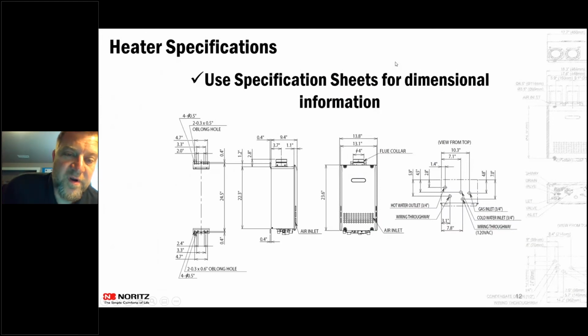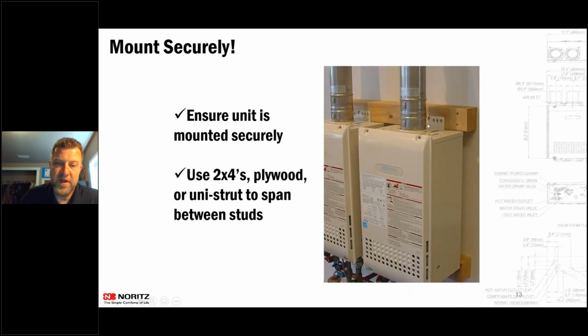So all tankless water heaters are going to have different types of mounting on how to mount it, but every single one of them is going to have an upper bracket and a lower bracket. At the top of these units, you can see here, there's this upper bracket up here. You're always going to want to make sure that these units are mounted level on the wall. This is a picture of some of the older units where you would span 2x4s across the wall, or people use unistrut or whatever you're looking to do to mount that to that wall.